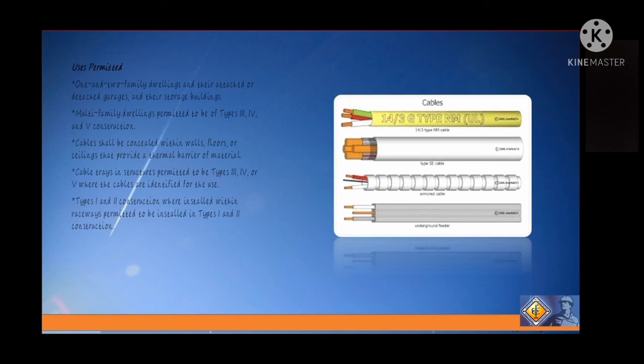For the uses permitted, one and two family dwellings and their attached or detached garages and their storage buildings. Also in multifamily dwellings permitted to be of type 3, 4, and 5 construction. Cables shall be concealed within walls, floors, or ceilings that provide a thermal barrier of material. And in cable trays in structures permitted to be type 3, 4, or 5 where the cables are identified for the use, and in type 1 and 2 construction where installed within a raceway permitted to be installed in type 1 and 2 construction.